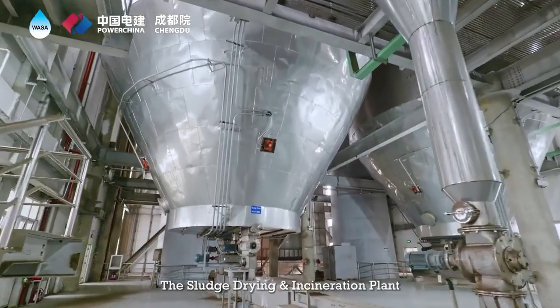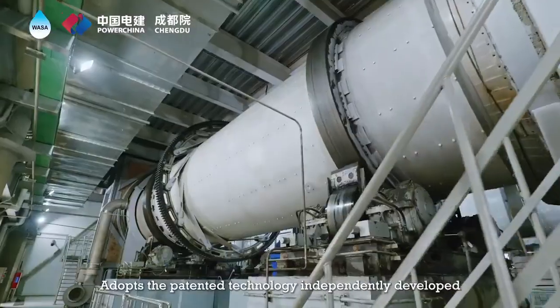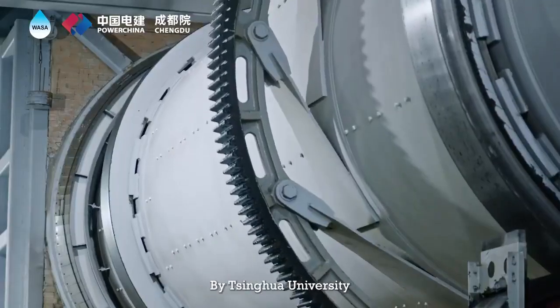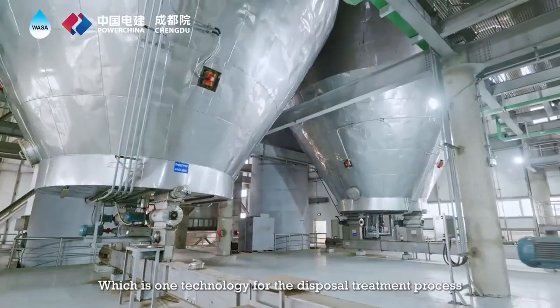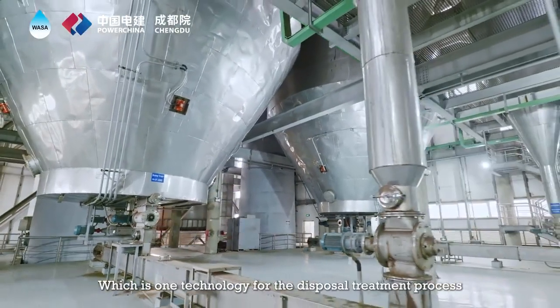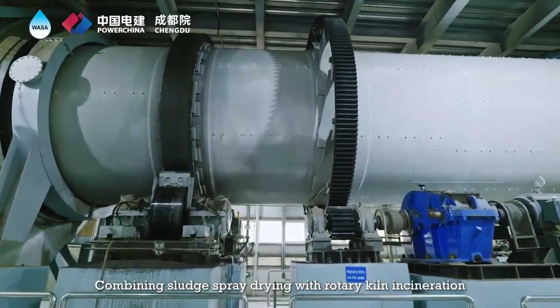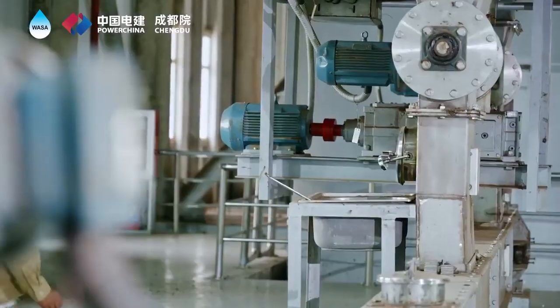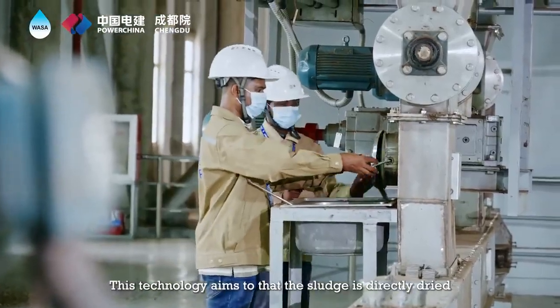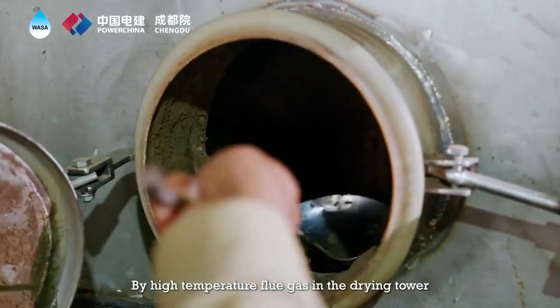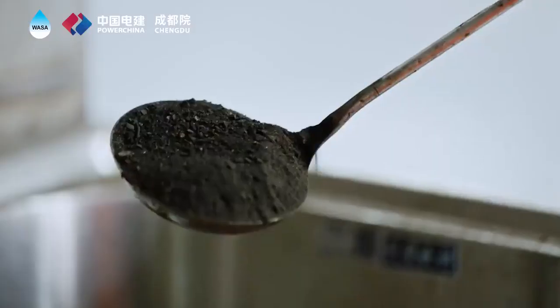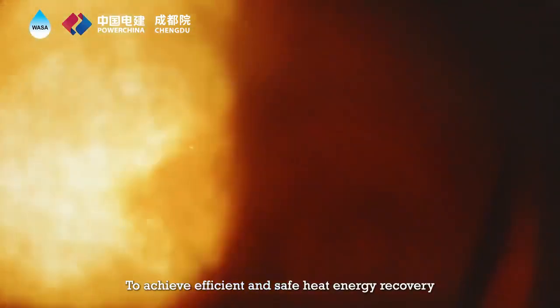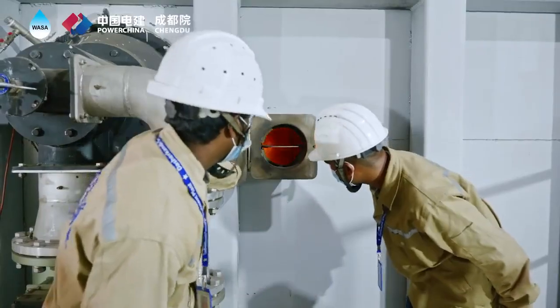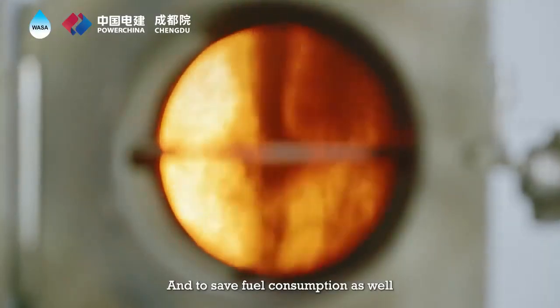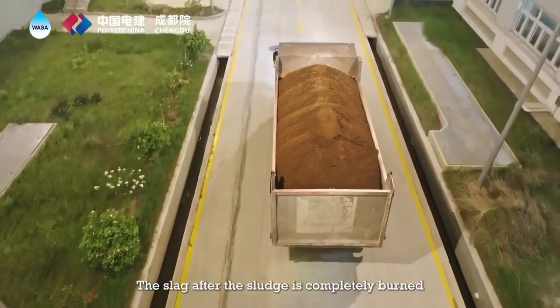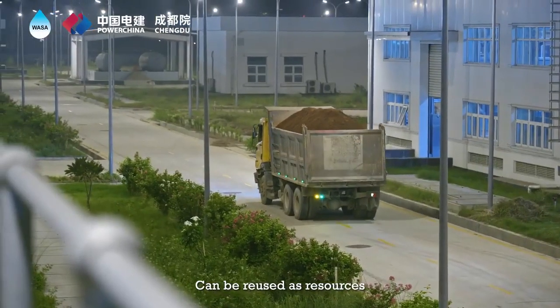The sludge drying and incineration plant adopts the patented technology independently developed by Tsinghua University, which is a technology for the disposal treatment process combining sludge spray drying and rotary kiln incineration. This technology aims to have the sludge directly dried by high-temperature flue gas in the drying tower to achieve efficient and safe heat energy recovery and utilization, and to save fuel consumption as well. The slag after the sludge is completely burned can be reused as resources.